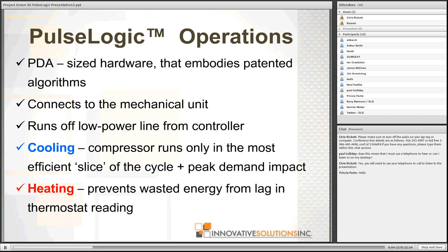We've taken a slice out of the compressor cycle. We developed this with the compressor manufacturers. Most compressors run the most efficiently if they don't operate for more than 6 minutes at a time. The refrigerant starts to heat up, and when it heats up, the atomization rate becomes less efficient, so then you have to run the air conditioner longer to achieve the same goal. That's one of the little things that we do on that.